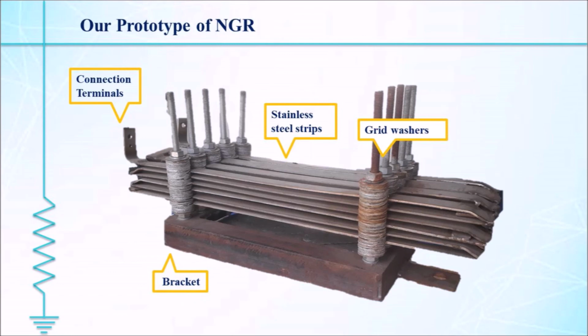Here, a bracket is used for holding all the setup of the device. A nut and bolt assembly is fixed on the bracket to carry resistive stainless steel strips. All the strips are connected in series and welded at each endpoint to complete the network. The strips are separated using insulating mica grade washers to avoid misconduction and internal short circuit. Two connection terminals are taken out, at the start for neutral and at the end for grounding connection. This is just a small demonstrative prototype of NGR.